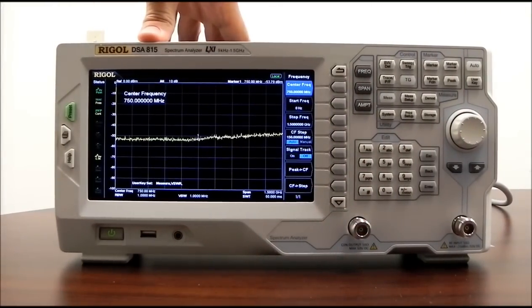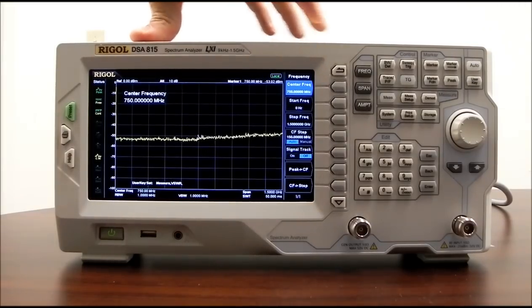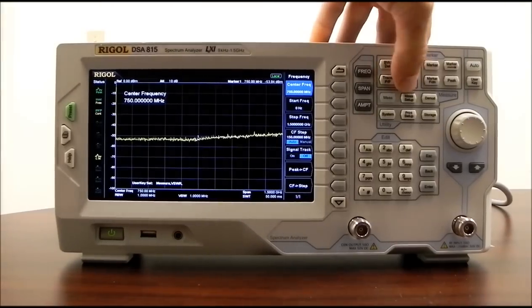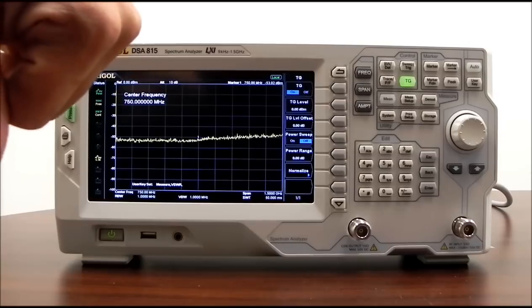The tracking generator output, for those of you that aren't familiar, is a frequency scanning RF source with an adjustable amplitude. So if we're scanning from 9 kHz to 1.5 GHz and we enable that tracking generator, we're going to have an output, in this case it is set to 0 dB.